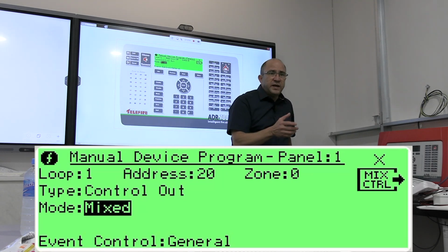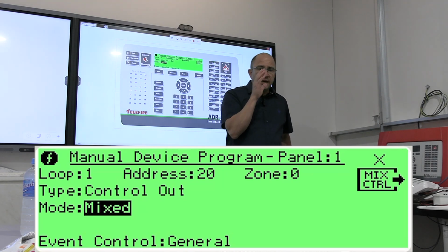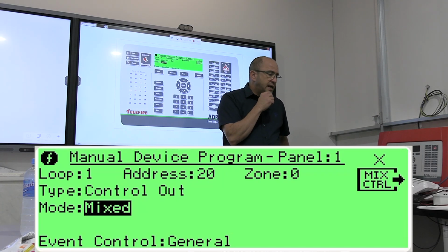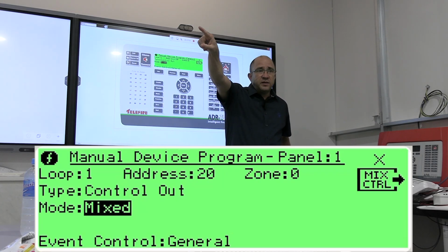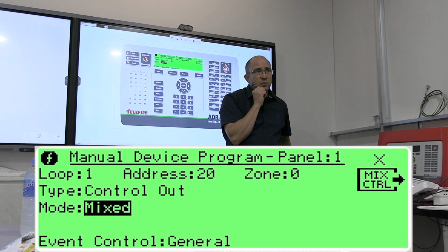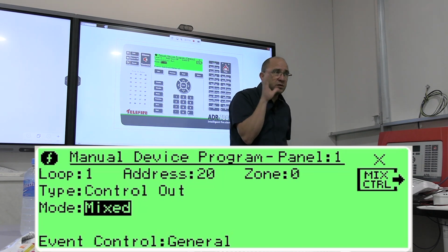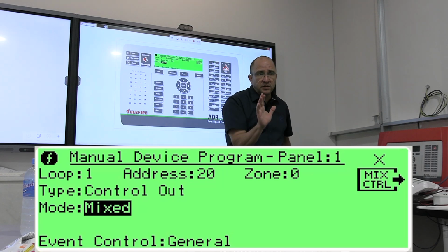And 3 years ago, we connected an output module in each door, 20 doors, okay? In order to open the magnets when there's fire. When there's an alarm with fire, or 2 alarms, or whatever, give a command to all the 20 doors, open the doors automatically. That's no problem up until now.